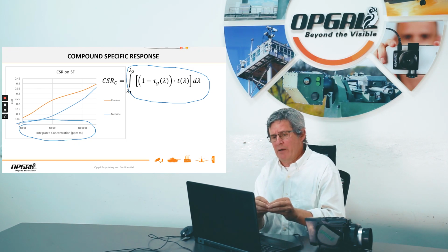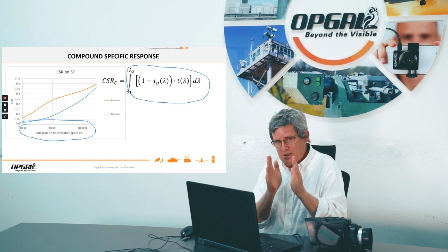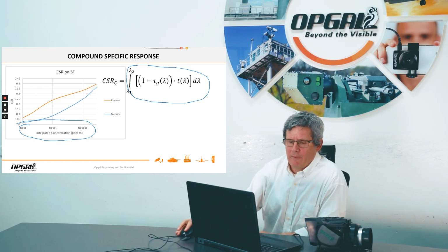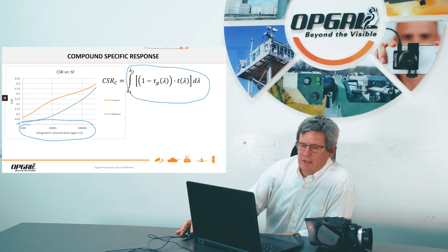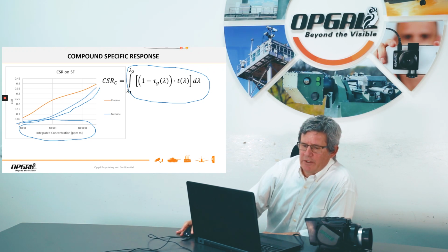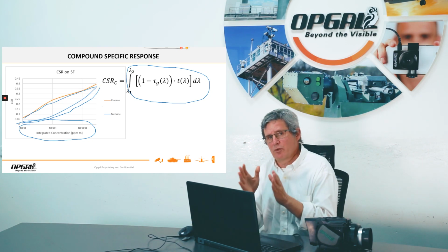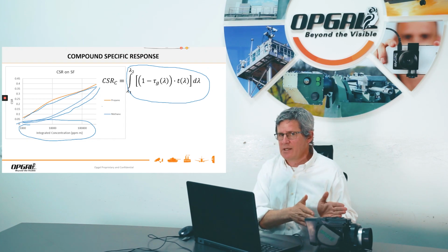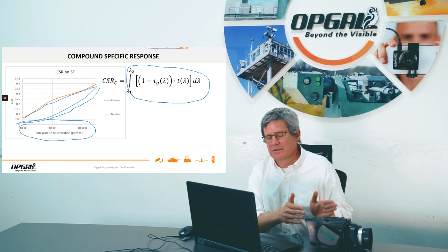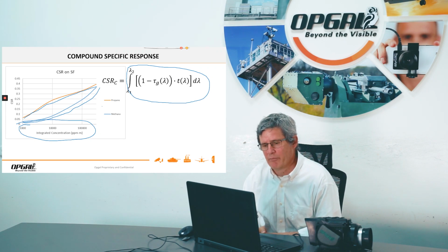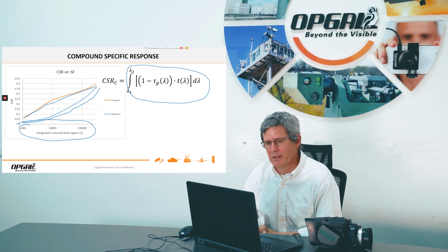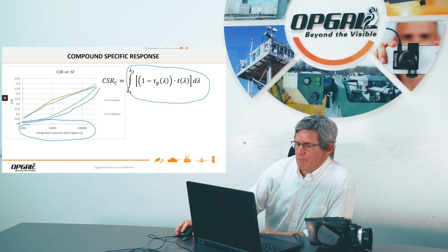So if it's fully absorbed, fully centralized inside the filter, like the methane, you can see that it will respond similarly to that curve. But if it's only partially, it will get saturated, so it will go this way for propane, where part of this absorption coefficient curve of propane is outside. We will see in later lessons how the difference between different compounds affects the response and sensitivity and range of these compounds.